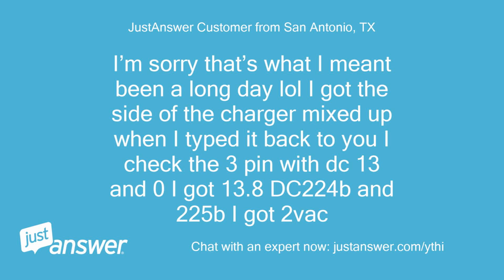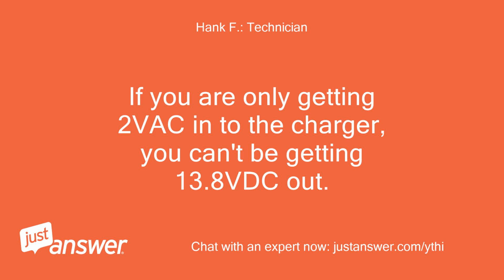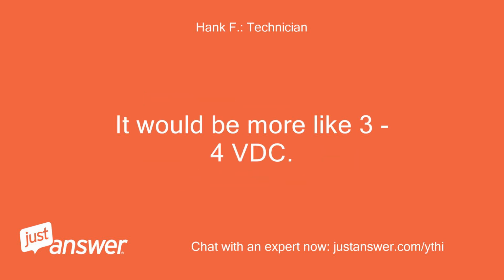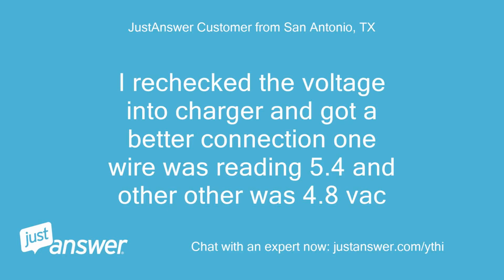I checked the 3-pin with DC 13 and 0. I got 13.8 DC. On 224B and 225B I got 2 VAC. If you are only getting 2 VAC into the charger, you can't be getting 13.8 VDC out. It would be more like 3 to 4 VDC. I rechecked the voltage into the charger and got a better connection. One wire was reading 5.4, the other was 4.8 VAC.